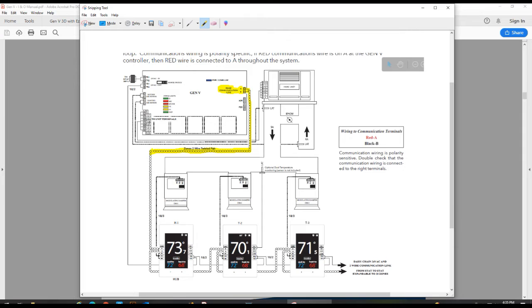We want to go ahead and run that to the first thermostat and land that at A and B and continue that daisy chain all the way through, landing on the A and B terminals. We want to make sure we don't use any wire nuts or butt connectors anywhere on the communication bus. It's critical to a clean and noise-free communication. So no wire nuts or butt connectors to be utilized there.